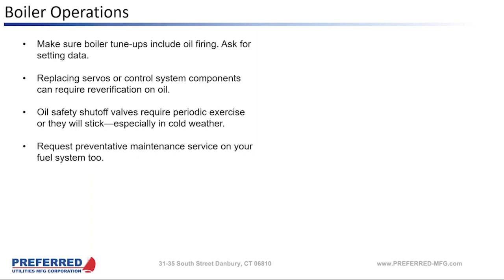So when you get a tune-up on your boilers, make sure they give you the tune-up setting data. You want to make sure that they set it up the way you want it. You want to make sure you're not smoking at any of the load points. And then you want that setting data available to your operators so that they know what normal oil operation looks like. Bear in mind that replacing a servo or control system components can require re-verification on oil. So literally anytime you have work done on your boilers, it's good to go back on oil and make sure that nothing on the oil firing was affected.